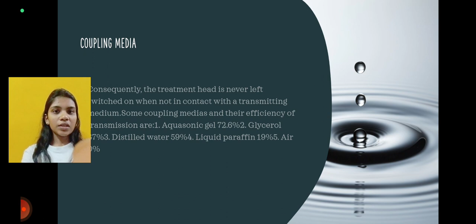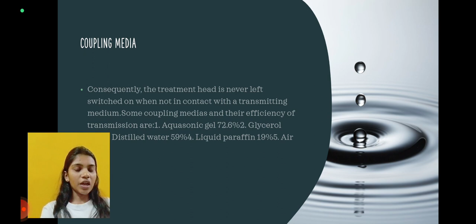Some coupling media and their efficiency of transmission are: first is aquasonic gel, at 72.6 percent. Second one is glycerol, at 67 percent, and third one is distilled water, at 59 percent. Fourth is liquid paraffin, at 19 percent, and air, at zero percent. There should be no air between the ultrasound head and the treatment area.